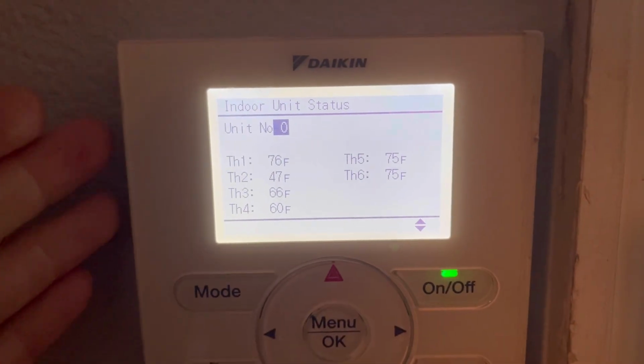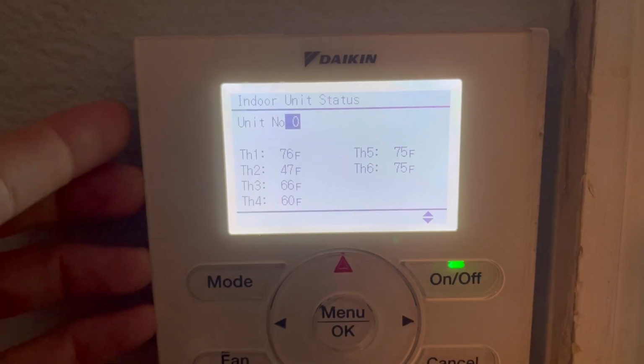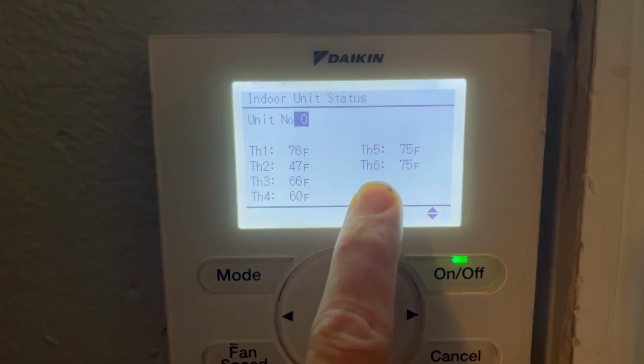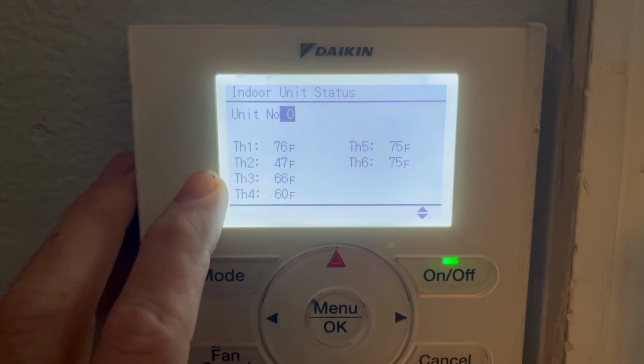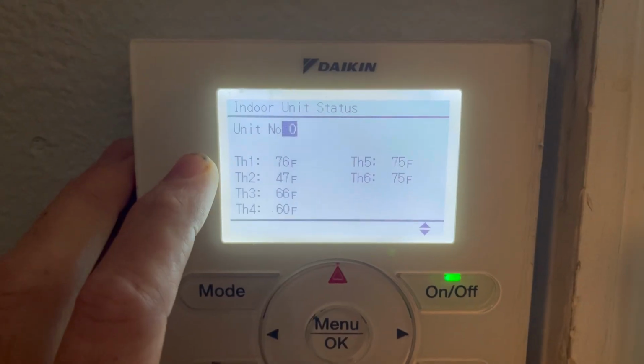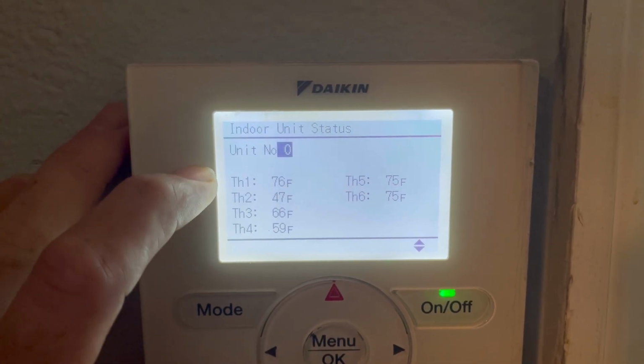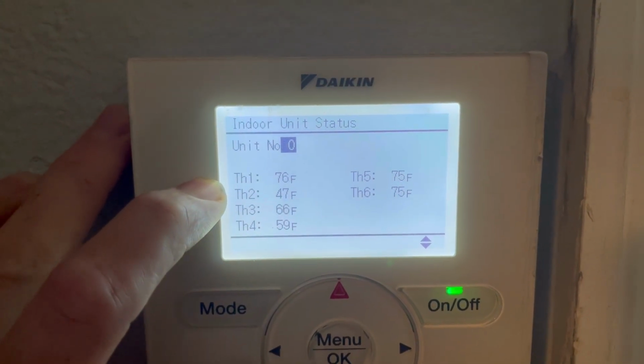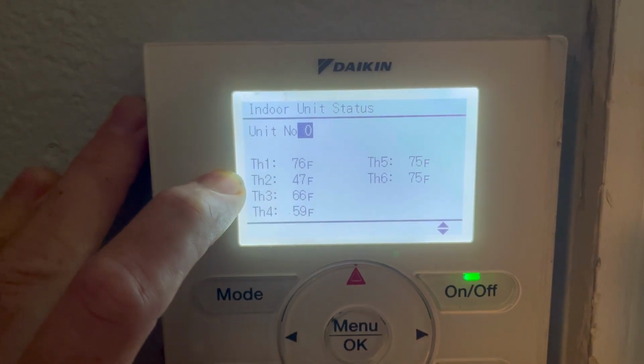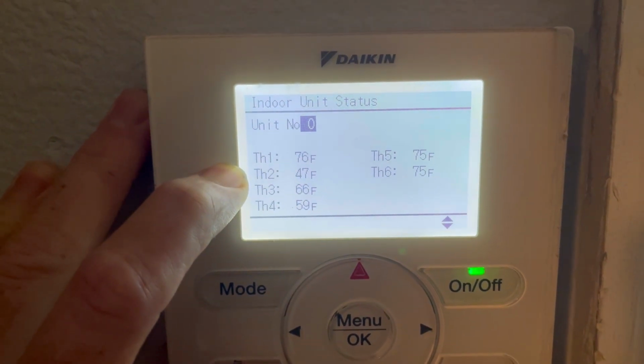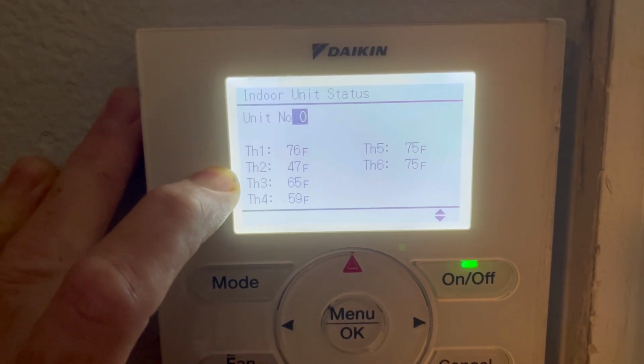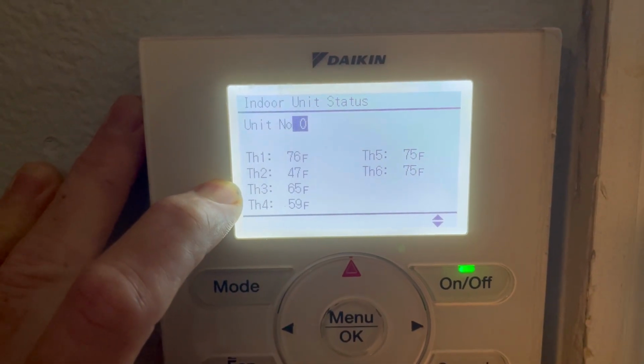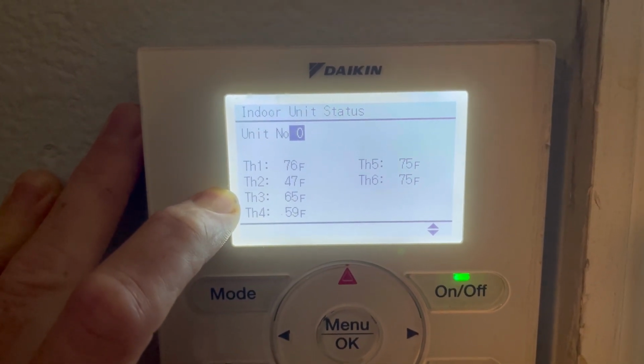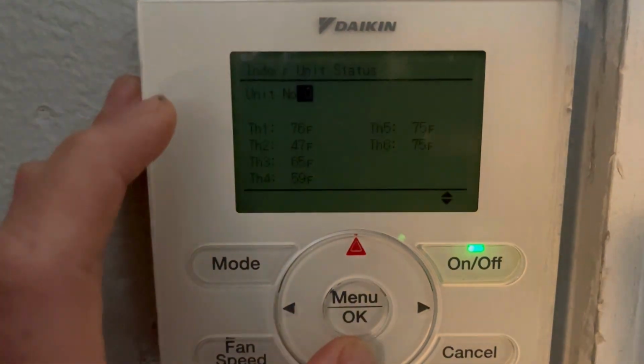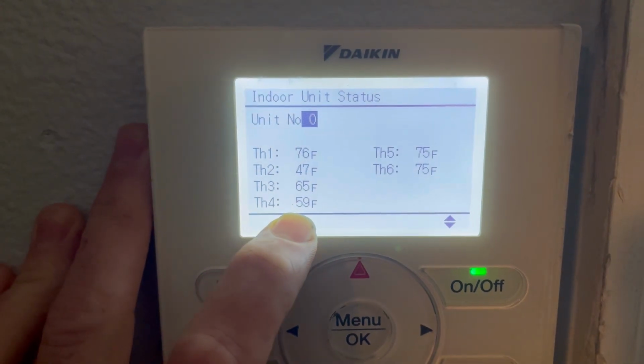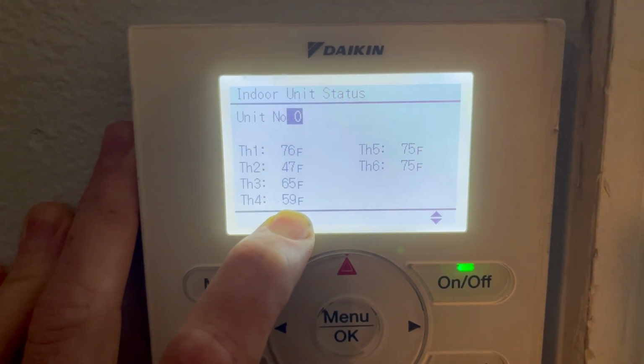I have an FXMQ PAVJU series. Specific indoor units will have all sensors listed. Not all units have the sensors. Older units like DQs don't have it. TQs don't have it. And you'll see here, I have return temp, 76 degrees. This is leaving my expansion valve, saturated vapor, TH2. This is my liquid sensor listed on service checker. TH3 is my suction thermistor. This is superheat leaving my coil. And then the 59 degrees is actually my discharge air temp leaving my evaporator coil, leaving my unit.